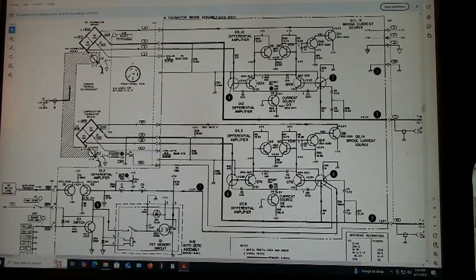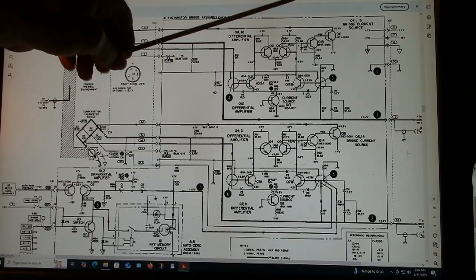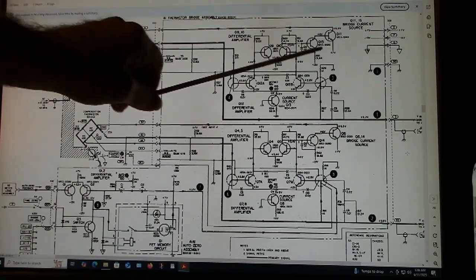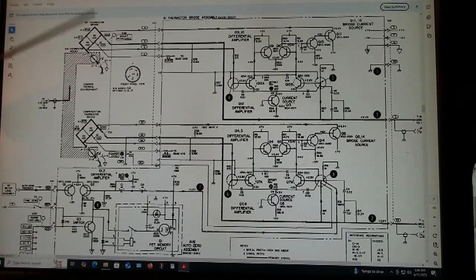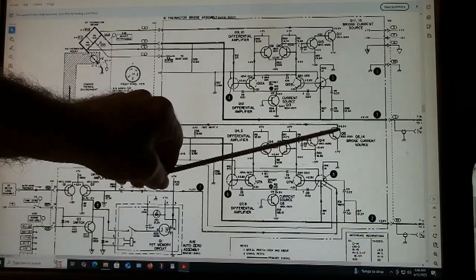They're matched thermistors, and as the temperature rises and decreases, these are negative temperature coefficient thermistors, their resistance will change equally. So this thermistor on the bottom is affected by ambient temperature only, and the thermistor on the top, you can see the RF coming in here. This thermistor will be changed, its resistance will be changed by not only ambient temperature but also by heating from the RF input applied here. They're thermally isolated here. Now the two bridges here are fed with a current source over here. The top bridge, the RF thermistor bridge, is driven by Q11 here, and the bottom thermistor is driven by Q6.